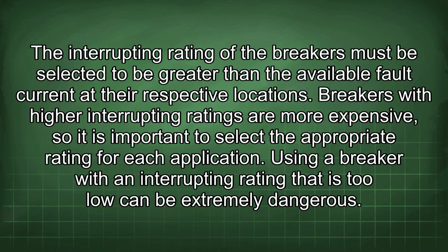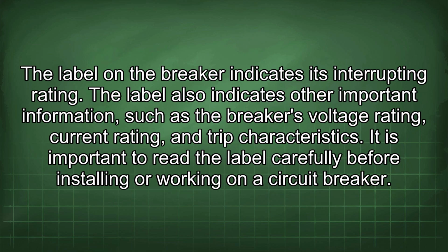The interrupting rating of the breakers must be selected to be greater than the available fault current at their respective locations. Breakers with higher interrupting ratings are more expensive, so it is important to select the appropriate rating for each application. Using a breaker with an interrupting rating that is too low can be extremely dangerous. The label on the breaker indicates its interrupting rating. The label also indicates other important information, such as the breaker's voltage rating, current rating, and trip characteristics. It is important to read the label carefully before installing or working on a circuit breaker.